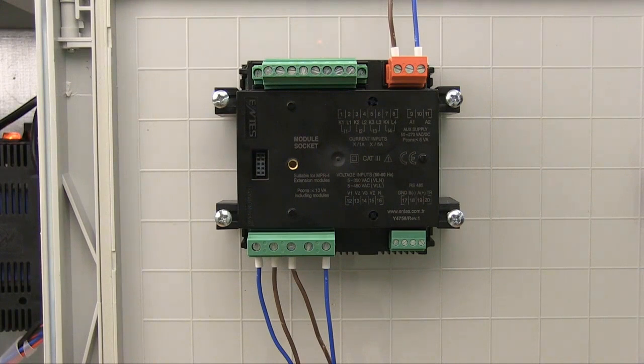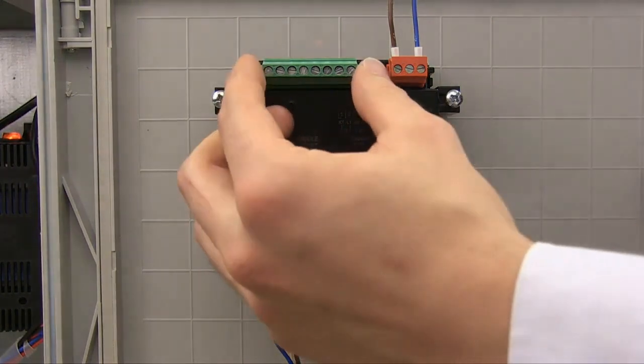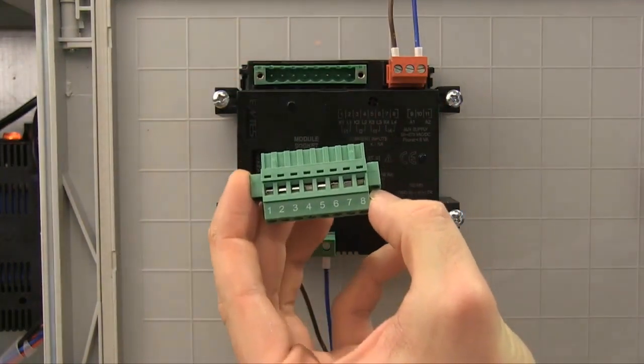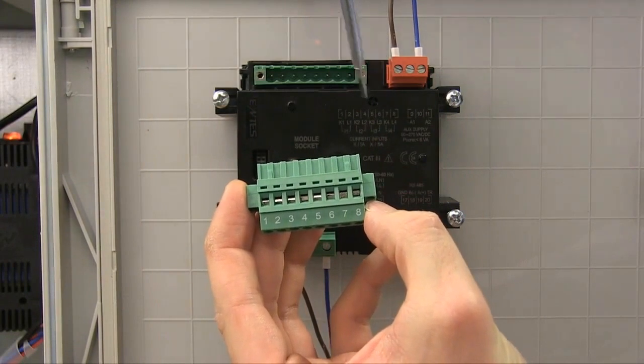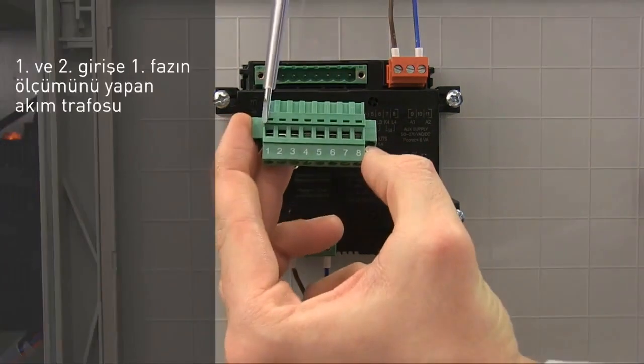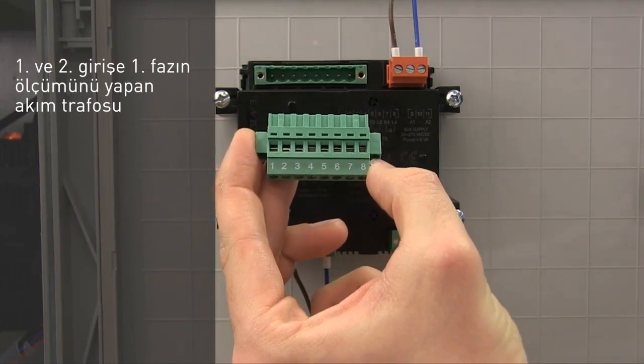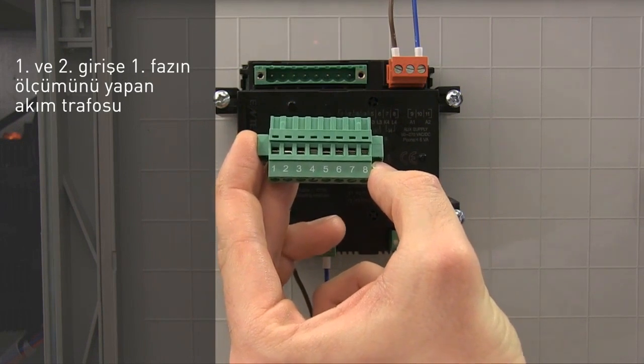Next, we are making the connections for the current transformers. The secondary K and L terminals of the current transformers are placed into the current terminals located at the top left corner of the MPR-4. Here, carefully noting the numbers on the back panel, we connect the first phase transformer to inputs 1 and 2.